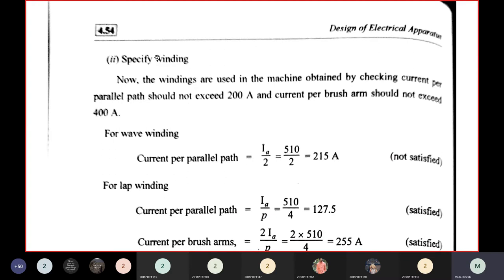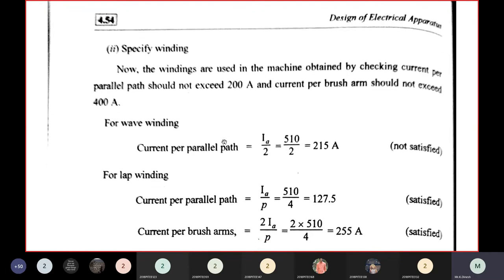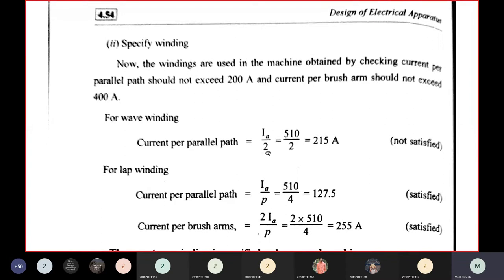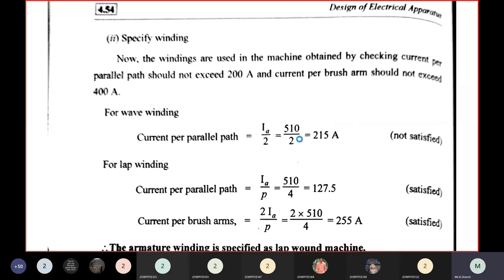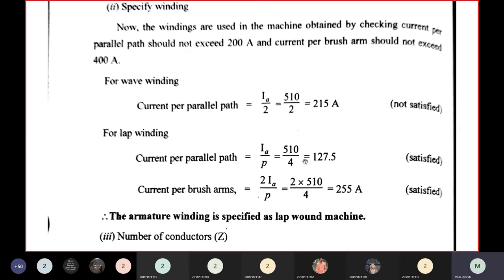To specify the winding: current per parallel path should not exceed 200 A. For wave winding, current per parallel path = IA/2 = 510/2 = 215 A — not satisfied. For lap winding, IA/P = 510/4 = 127.5 A, which is less than 200 A — satisfied.